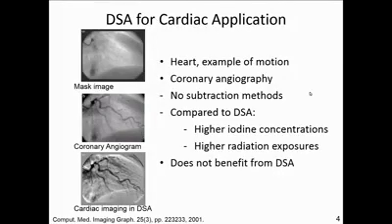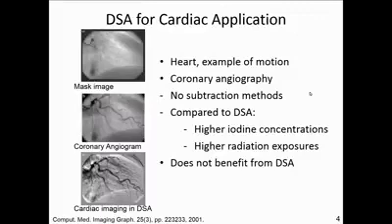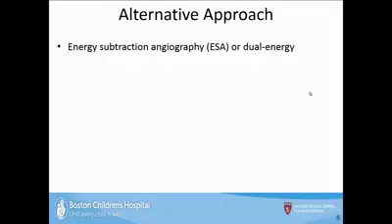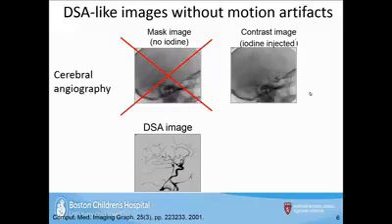When mask and contrast images are subtracted, even with motion correction, cardiac imaging does not benefit from DSA. Motion artifacts compromise image quality. So we have this gold standard in vascular imaging that we can't use to image a critical structure. An alternative approach is known as dual energy, or as I've been calling it throughout my career, energy subtraction angiography — ESA — which aims to eliminate the need for a mask image.